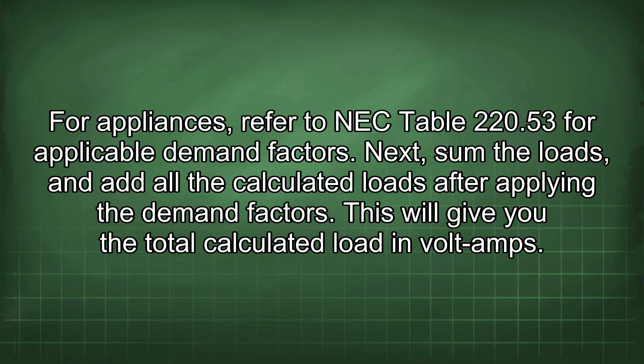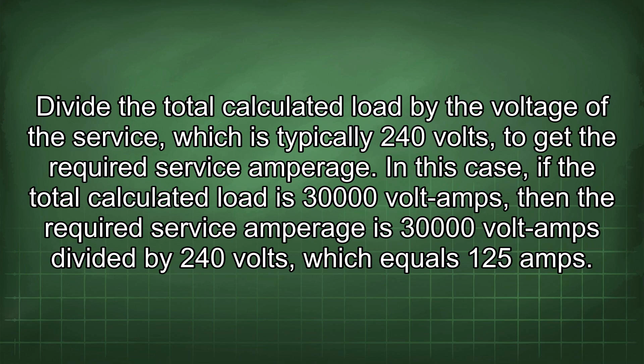Divide the total calculated load by the voltage of the service, which is typically 240 volts, to get the required service amperage. In this case, if the total calculated load is 30,000 volt amps, then the required service amperage is 30,000 volt amps divided by 240 volts, which equals 125 amps.